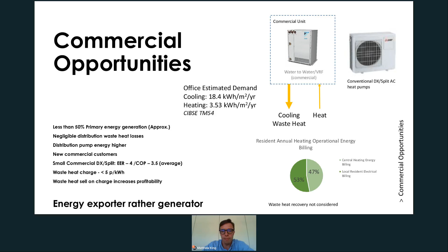Looking at a small scale retail unit, they're conventionally using heat pumps, so DX or split units for heating and cooling, with cooling COPs around 4 or so. So their cost per kilowatt, based on 20p per kilowatt hour, is about 5p. Looking at the revenue opportunity there, you're able to charge them slightly less, because you're then charging residential units and other customers for using that heat to generate domestic hot water in summer, or both space heating if there's a simultaneous heating and cooling demand. So looking at the economics is quite an important start to the fifth generation approach, and it can be almost comparable when you think about it - that's just in an operational sense.